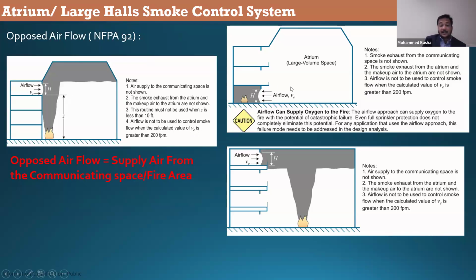This kind of system is a more critical system, because there's a caution here. Assuming a fire happening in a communicating space, the fire is not happening in the atrium, whereas in this figure the fire is happening in the atrium, but here the fire is happening in the communicating space. So we do not want the smoke to come out of the communicating space to the atrium space. So we will be introducing the fresh air into the fire area.